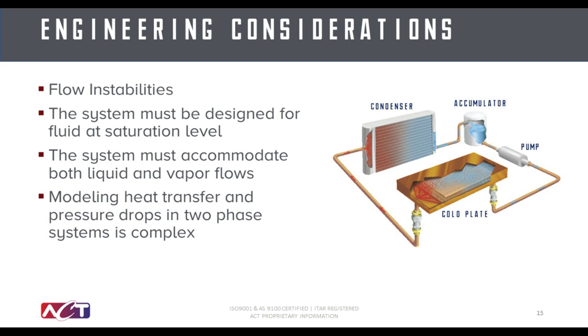Now that we've discussed the benefits of pumped two-phase systems, let's discuss some engineering considerations. The first question that often comes up relating to two-phase systems is related to flow instabilities. Flow instabilities can occur in a pumped two-phase system that's poorly designed if the system is allowed to violently boil and push fluid back out the inlet of the channels. This occurs when the fluid reaches a superheated condition before it exits the cold plate and violently boils, forcing liquid back out the inlet. In a properly designed two-phase cold plate, the system always finds an appropriate place to boil, and the fluid is always moving in the proper direction. ACT has years of experience developing evaporators for two-phase systems to avoid this situation.